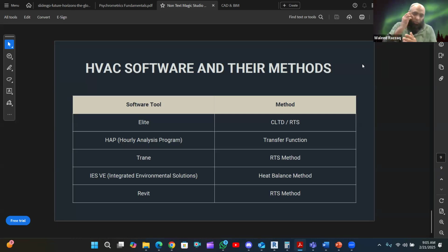Why do I ask this question? Because there is cooling load and then there is energy modeling. The result of cooling load, whether in tonnage or BTUs, 12,000 BTUs is usually referred to as 1 ton, or the metric unit is kilowatt. Not the electrical kilowatt, but the kilowatt of cooling load or heating load, because that parameter is power.